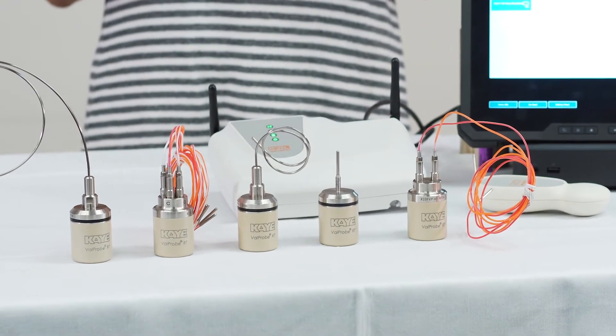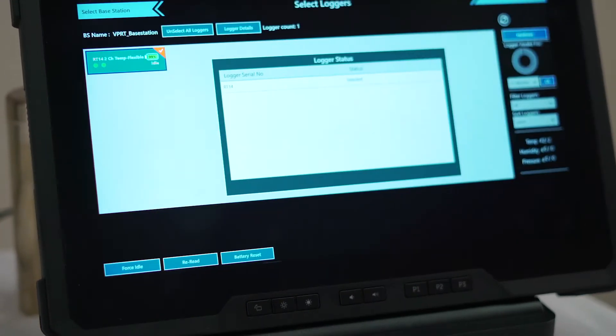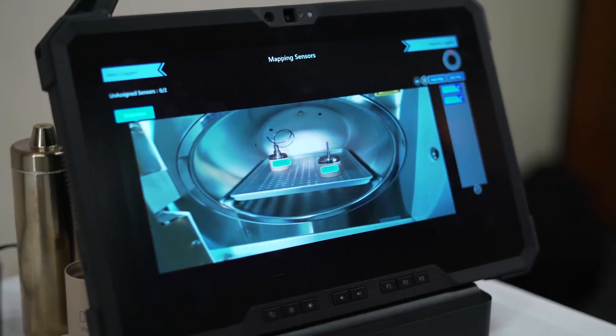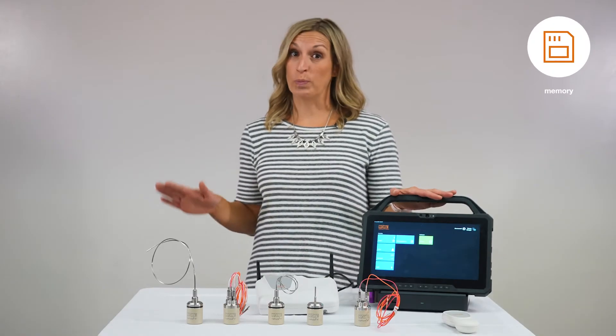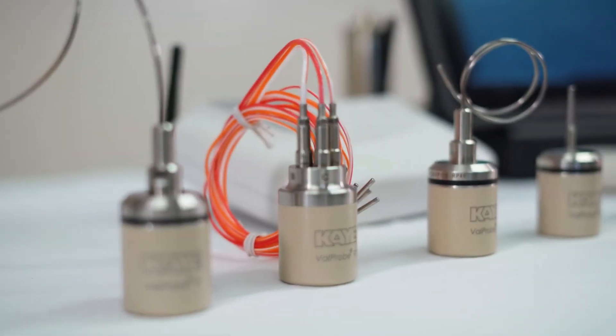Another enhancement with our real-time ValProbes is there's no more reader, so there's no time wasted programming these loggers. You can immediately program them by waking them up and setting them up within the software. Once the study is completed, you get your data immediately. If you're not watching the real-time data, you can disconnect the tablet, do reporting and other tasks, then come back and reconnect to view the data on your base station.